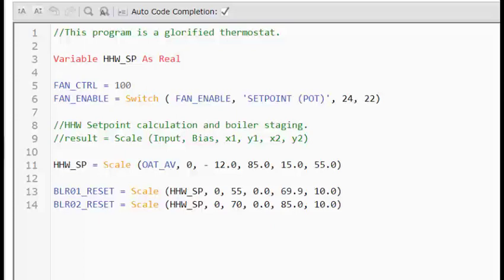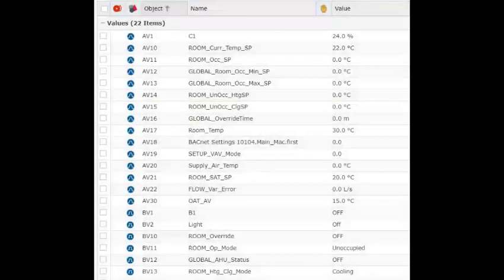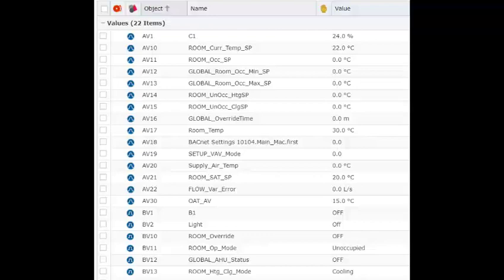If you want a piece of information only kept locally on the program so that nobody else can see it, then you would use a local variable. But if it is something that needs to be on the graphics or shared on the network or with another program in the controller, then it would be better to use an AV or a BV object to store this information. It depends on what you're trying to do as to what's the best way to do this.